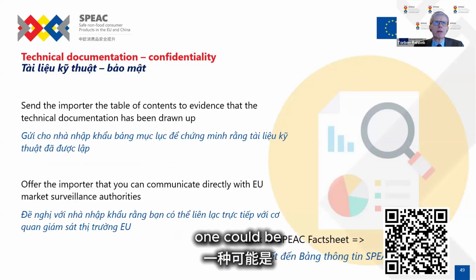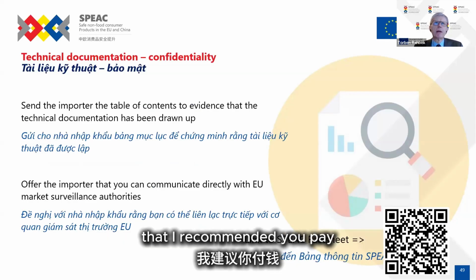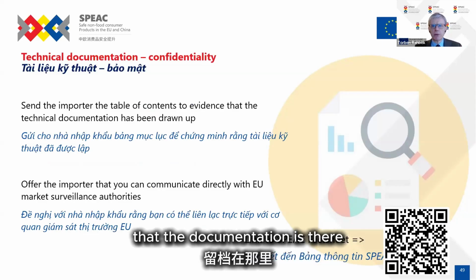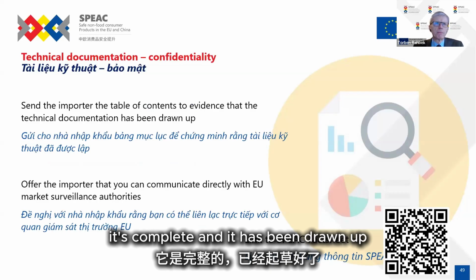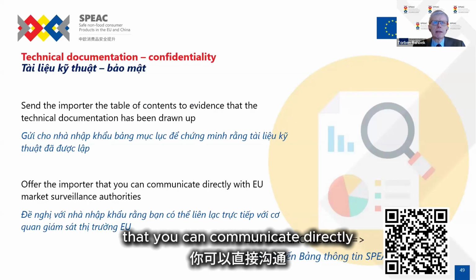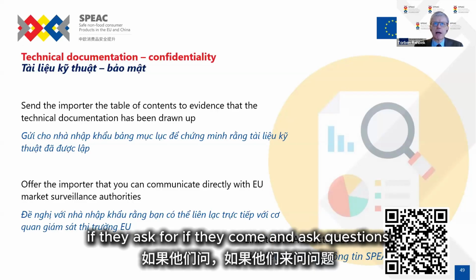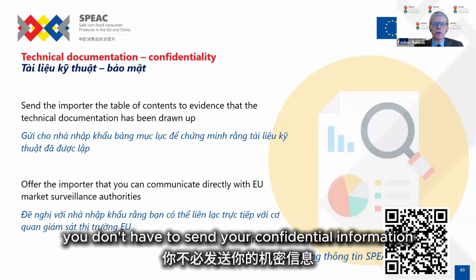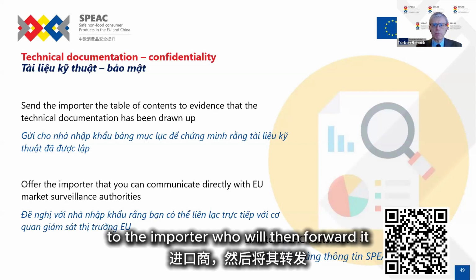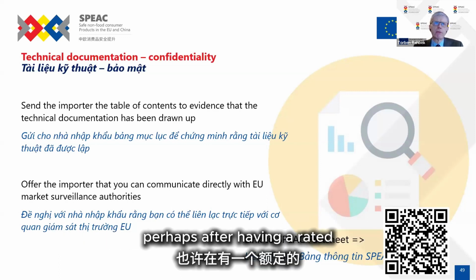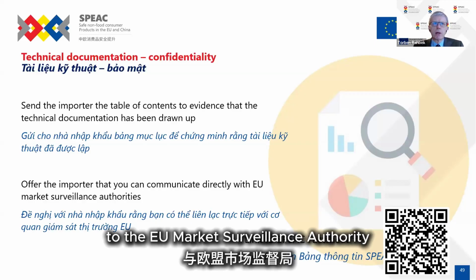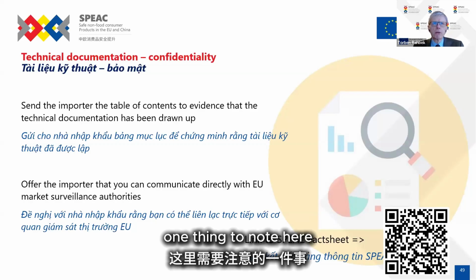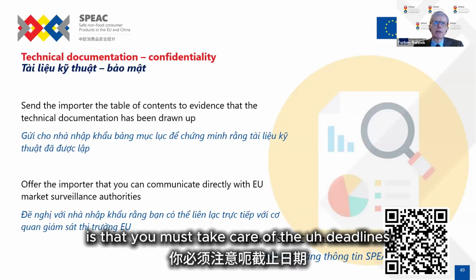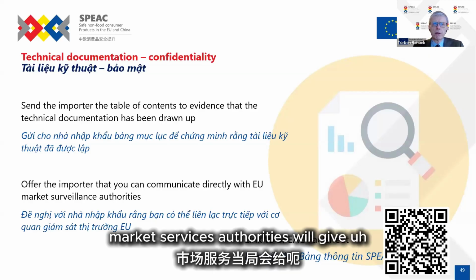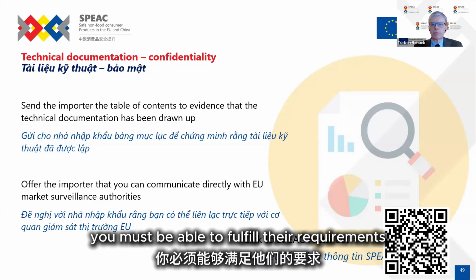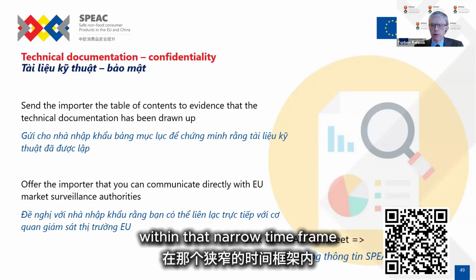Two ways to circumvent this. One could be that you could send the importer the table of contents that I recommended you build, because it could show the importer that the documentation is there, it's complete, and it has been drawn up. You can also suggest to the importer that you can communicate directly with EU market surveillance authorities if they come and ask questions. Then you don't have to send your confidential information to the importer, who will then forward it, perhaps after having read it. But you can communicate directly to the EU market surveillance authority. One thing to note here is that you must take care of the deadlines. Normally, market surveillance authorities will give people like 2 weeks to reply. You must be able to fulfill their requirements within that narrow time frame.